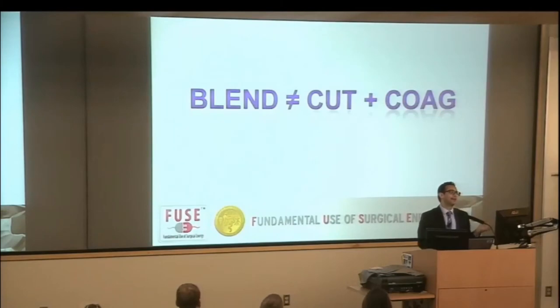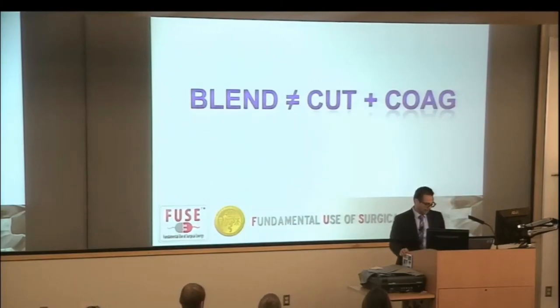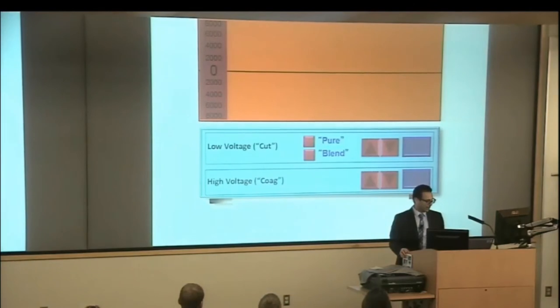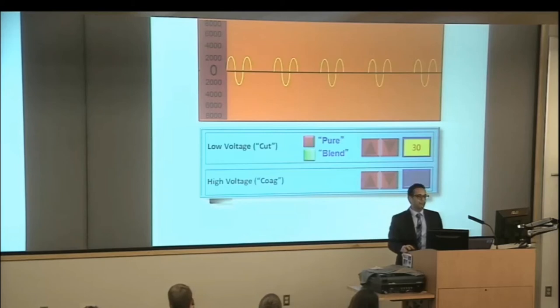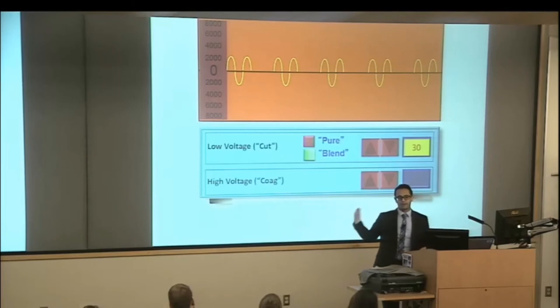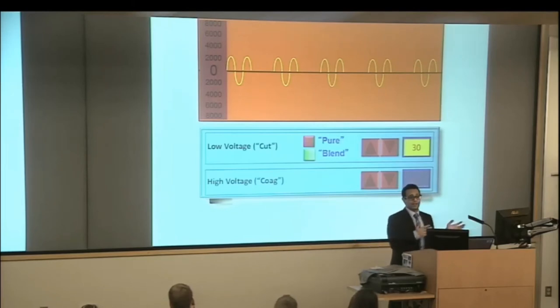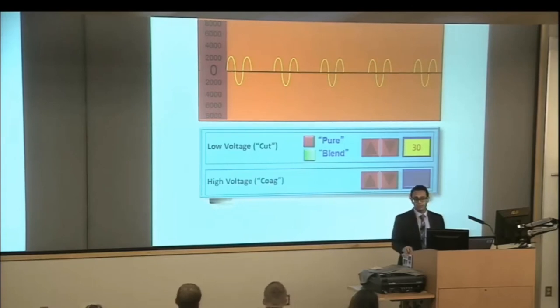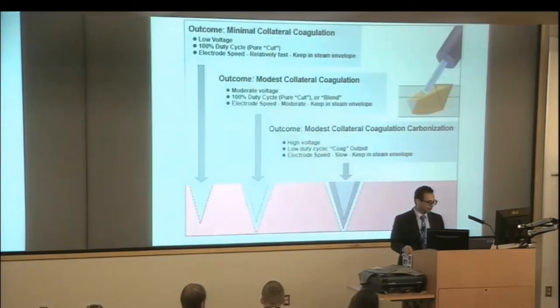What about blend? We have that function as well on the ESUs. What does that mean? It's not cut plus coag. Basically, you use blend when you press the cut button, but you have to ask the float nurse to actually put the device on blend. When you put it on 30, you get something in between. So duty cycle is a spectrum: on one end you have 100%, which is cut; on the other end you have 6%, which is coag; and in between settings is where blend comes in, giving you a 50% duty cycle.